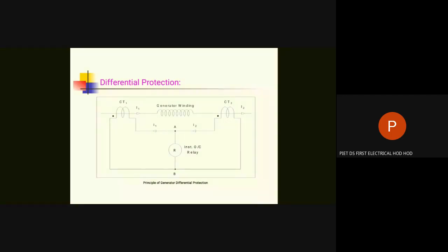Overhang means the conductors are going from slot number 1 to slot number 7, and that is going behind the generator. That is known as the overhang portion. In this overhang portion, R is crossing Y or Y is crossing B. So there the insulation between R and Y can fail. And there can be a failure of insulation between phase and ground. And this is possible in generator slots also. So that is a line to ground fault. So we have to talk about both kinds of faults, double line and line to ground.